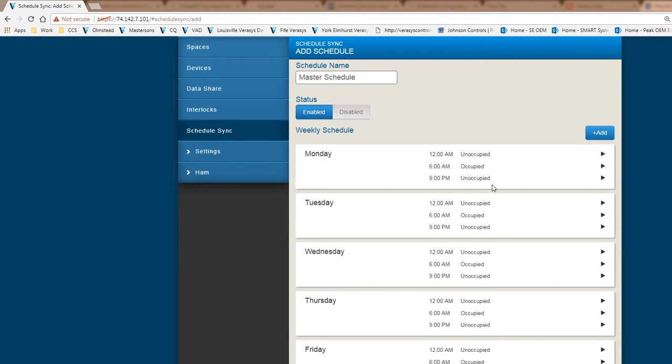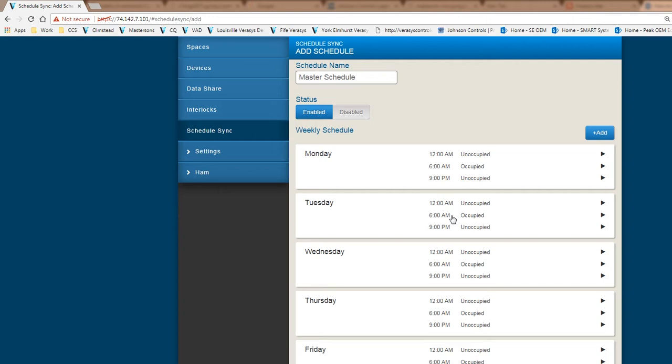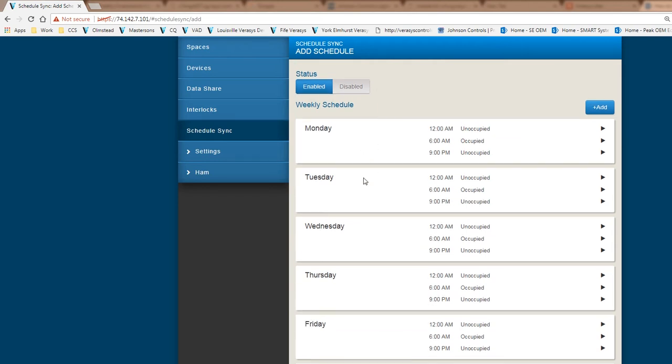The reason for this is that the BACnet object that we're using, when it switches to the next day, has to know what is the state that you want to be in. Even though I have 9 o'clock unoccupied, I've got to force another unoccupied period at midnight when it rolls over to the next day so it knows it needs to be unoccupied till 6 o'clock in the morning. This is just a little bit of extra step for version 1.0, but in the next revision you wouldn't have to do this.